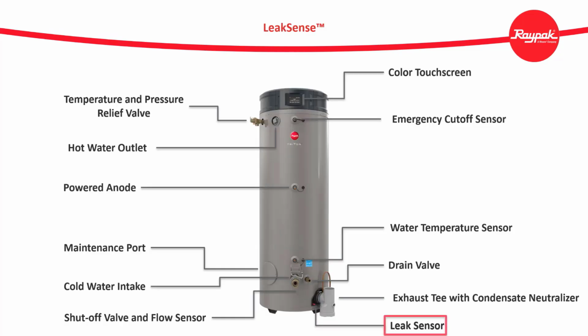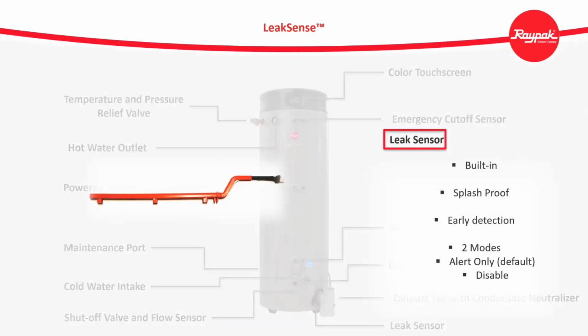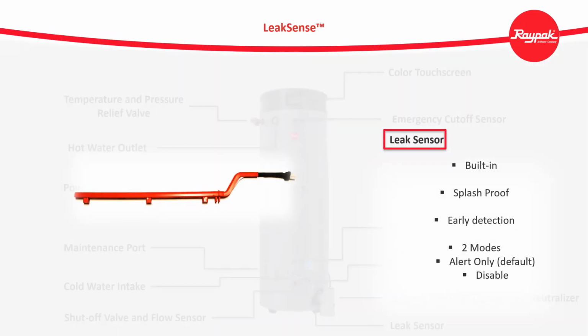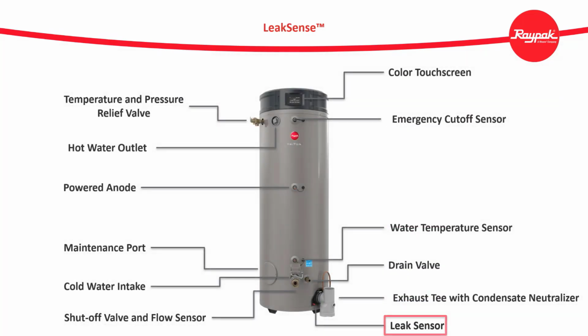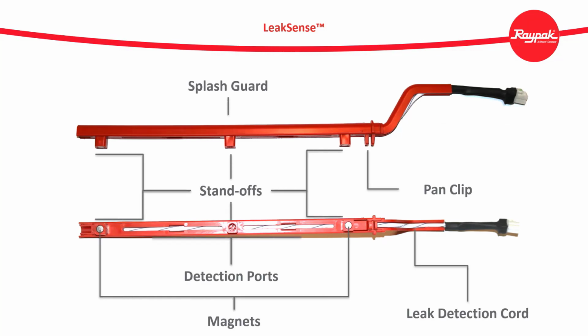Our leak sensor clips onto the pan. As you can see, the LeakSense tool is intelligently designed, with magnets to keep it in place in the pan and small standoff feet to keep it slightly elevated. This design avoids false positives from minor splashes. The open slots in the bottom allow for water to contact the leak detection cord when there is an actual leak.